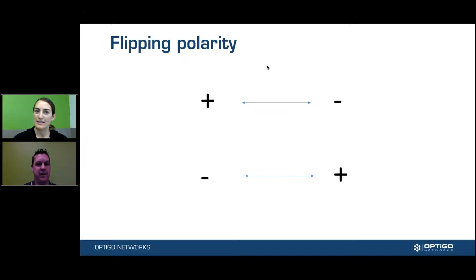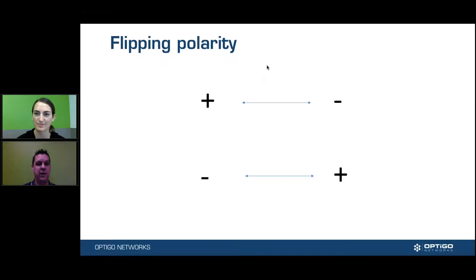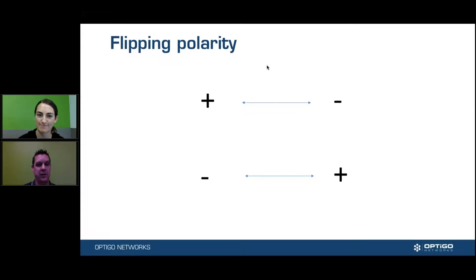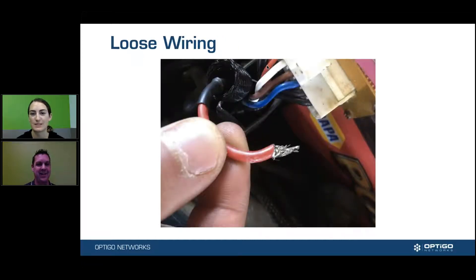Flipping polarity is a pretty bad one. When you go from one MSTP device to the next, the wires inadvertently get flipped. Even worse, if you extend your wires to a junction box and maybe the color of the wire changes and you're not sure which is which — it's not hard to do. It does happen and it's sometimes very hard to find, especially if the wires change color.